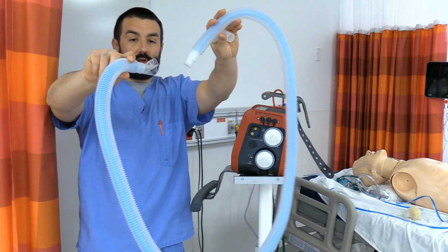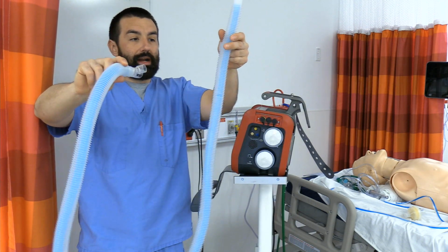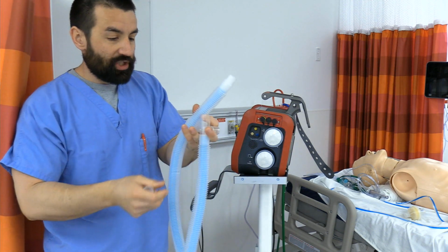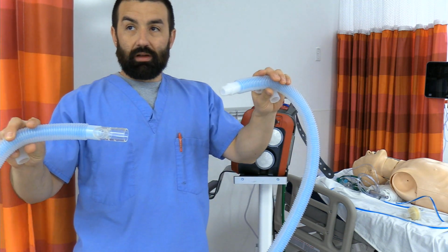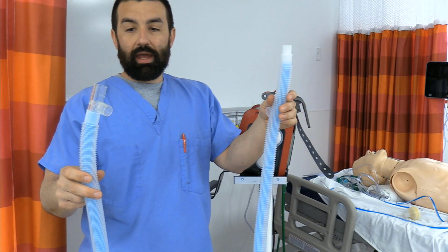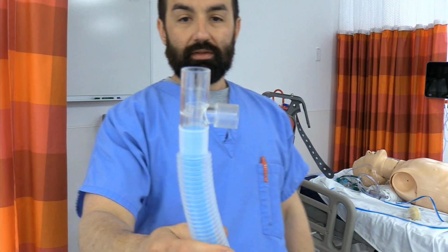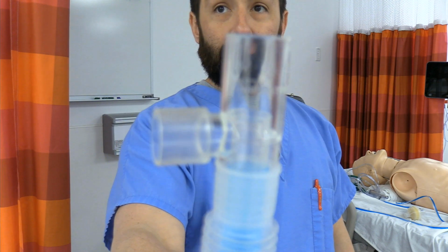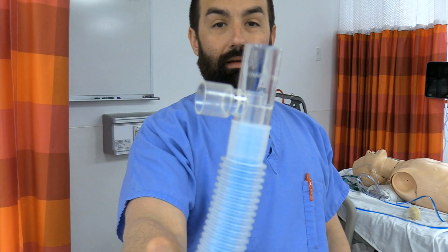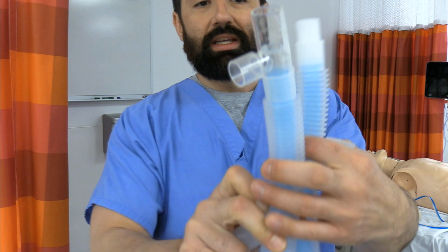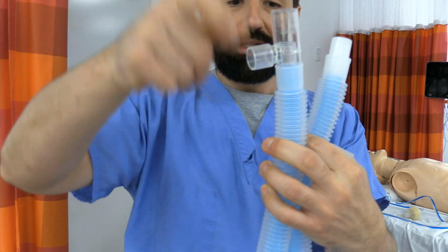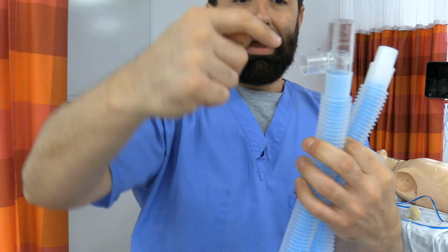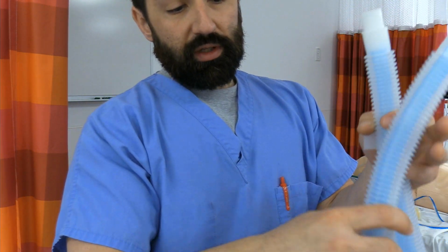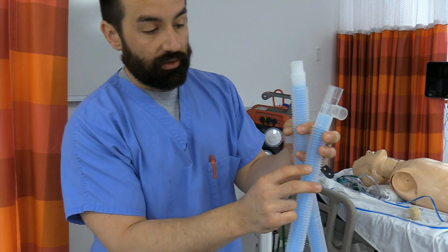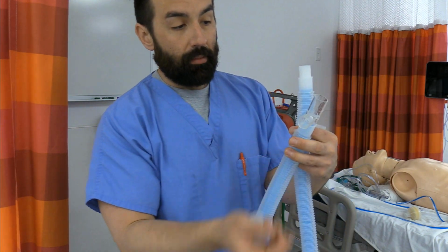It's a transport circuit. It's a dry circuit, so non-heated wire, so we use passive humidity with an HME. And it looks like a single limb, so it's single limb for simplicity and not getting hung up on things, but it's actually a circuit inside of a circuit. So if you look really closely, I don't know if you're going to be able to read that. It says inspiratory. You can see there's a little blue circuit inside of this clear circuit. That's going to carry gas to the patient. And then this other part, exhalation is going to take place through this bigger appearing clear circuit, but it's actually going around the inspiratory and coming out through the side right here.